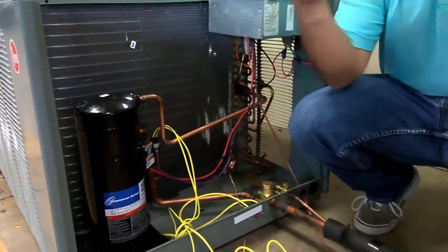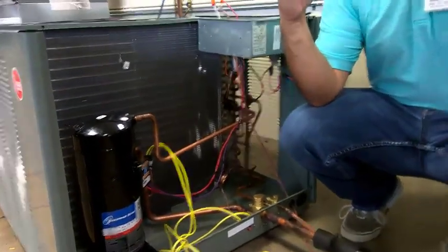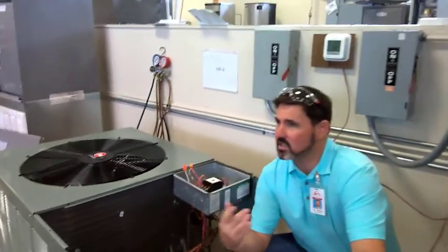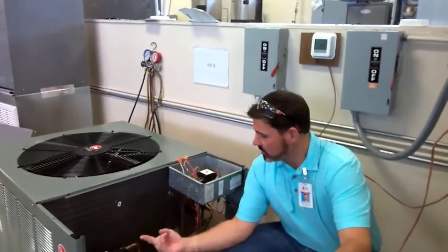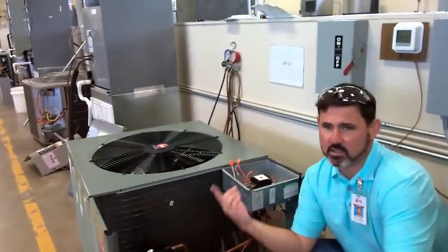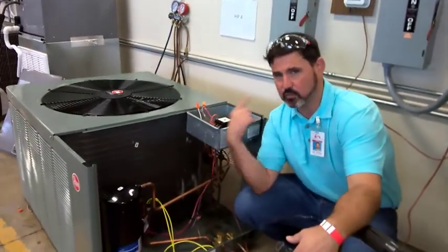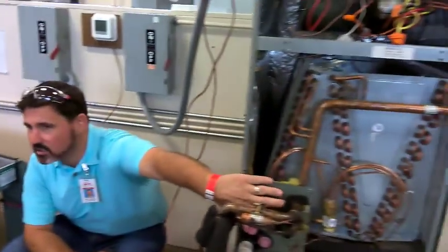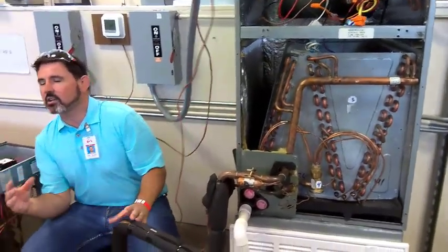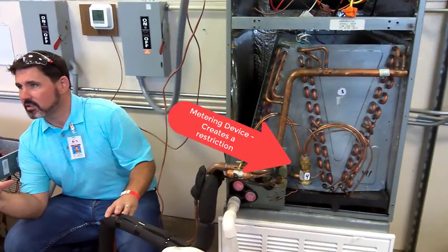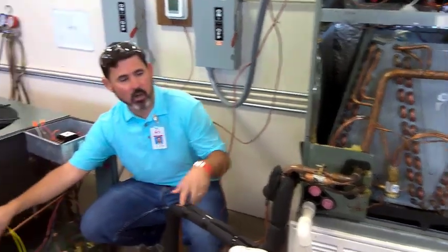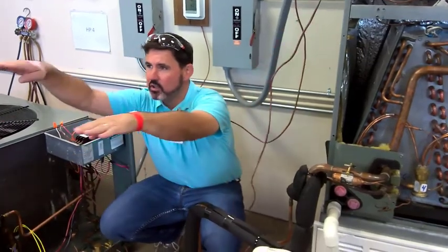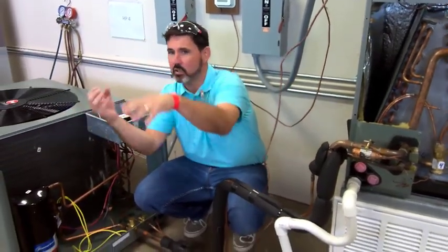All right, a compressor is what we call the heart of the system because it pumps refrigerant throughout this system. Alone, pumping refrigerant is basically just a circulating pump. All it's doing is moving refrigerant in the system. Now, eventually, we're going to hit this component over here that's called our metering device, and it's going to create a restriction. So when you have this pumping and you have a restriction, you end up with a pressure difference. So you end up with a high side and you end up with a low side.